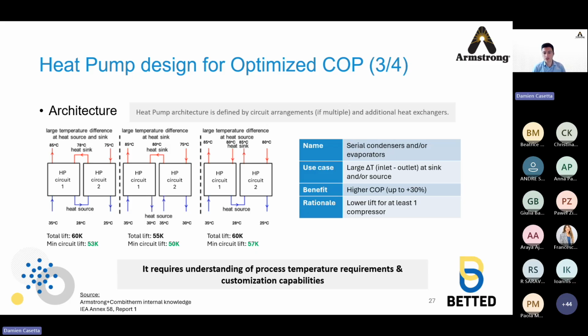Then comes the architectures of heat pump. So the architecture is how you are arranging circuits and how you are inserting additional heat exchangers beyond the main ones that we've just seen. In this example, we are showing the serial condensers and evaporator technique, which is basically making use of the large temperature difference that you can have between the inlet and the outlet of the hot and the cool side of the heat pump. And with this, you can get a higher COP up to 30%.